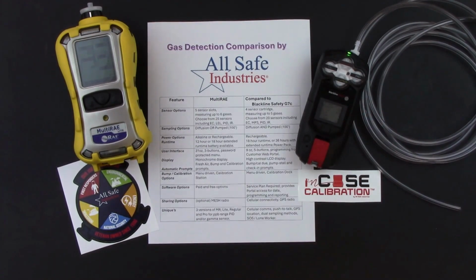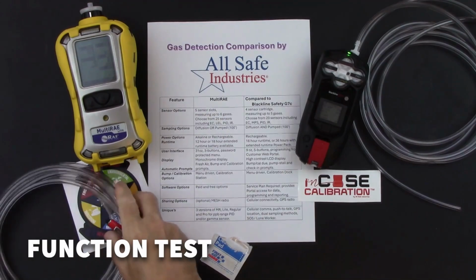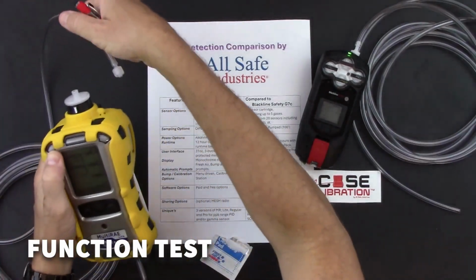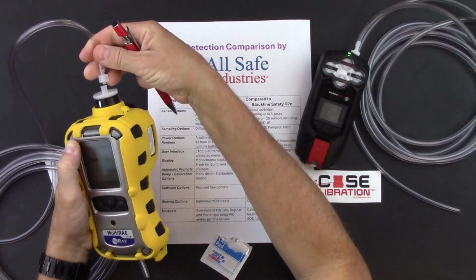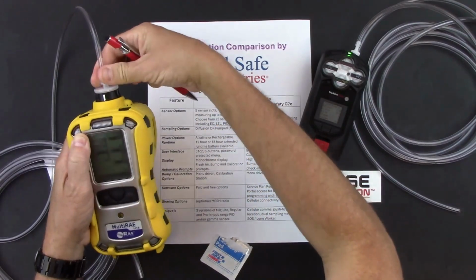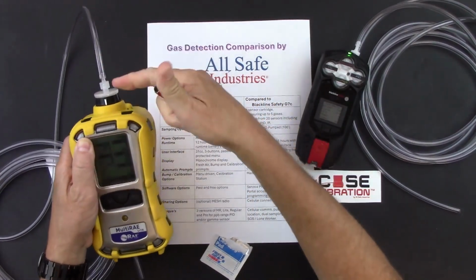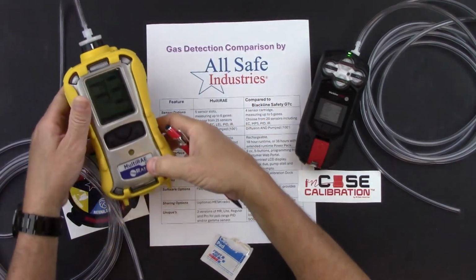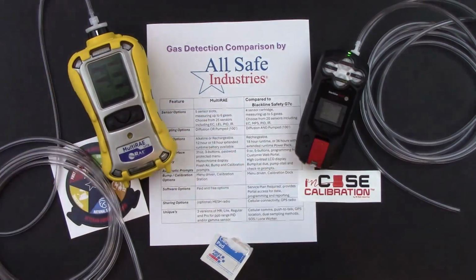So let's go ahead and run that comparison test just so that we can see the pump draw and the comparison of the response to the PID sensor to a simple alcohol wipe. So let me attach some tubing to my MultiRAE. This is a luer fitting connection, so you want to make sure when you attach that luer fitting that it's a good snug fit so that you don't bring in any fresh air and dilute out your gas sample.